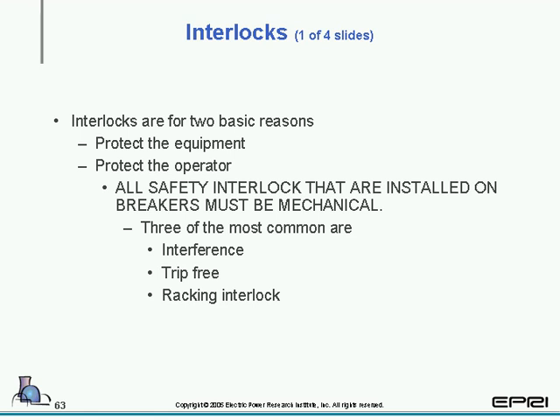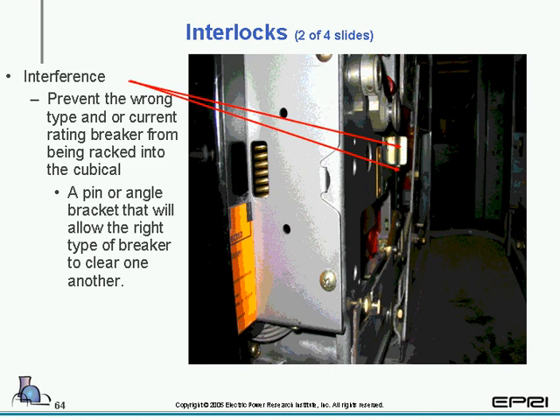Interlocks. Interlocks exist for two basic reasons: protection of the equipment and protection of the operator. And the thing to keep in mind is all safety interlocks that are installed on a breaker must be mechanical for human protection. Three of the most common are interference, trip-free, and racking interlock. An interference angle prevents you from racking the wrong type of current or voltage-rated breaker into a cubicle. In this particular design, we have an angle and we have a pin. And you'll see that when this breaker can be racked in, the angle will clear the pin, letting this interlock allow that particular design breaker into the cubicle.